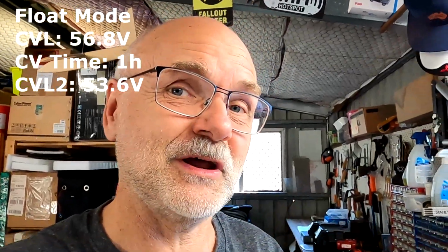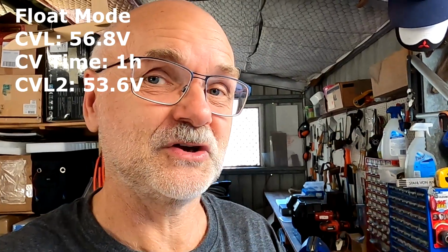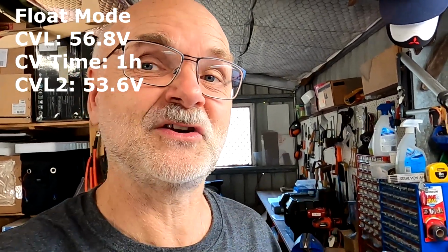With this in mind, Seplos could easily update the software and implement more features, like for example a float mode. When we hit the CVL, the charge voltage limit, it stays there for an hour and then reduces the charge voltage limit to another set value, and tells the solar charge controller to lower the voltage. So it keeps the battery 100% charged, but on a lower voltage. That would be a very easy feature to implement and would make this the best BMS on the market.